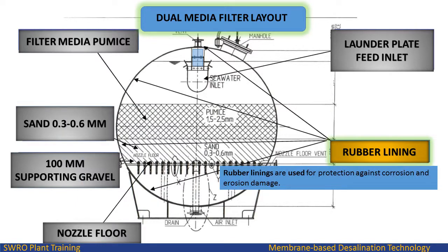In the nozzle floor, nozzles are used with a slot size of 0.2 millimetres. The final filtered water comes from the nozzle output. Rubber linings on the inner surface of the dual media filter vessel are used for protection against corrosion and erosion damage.